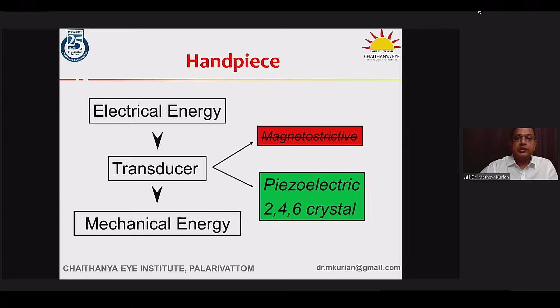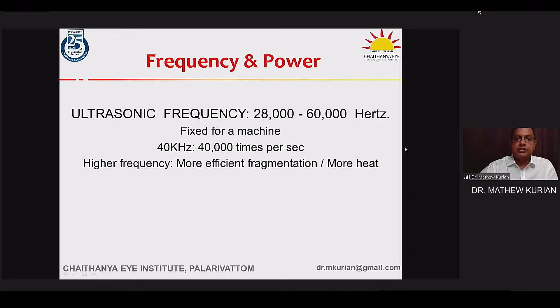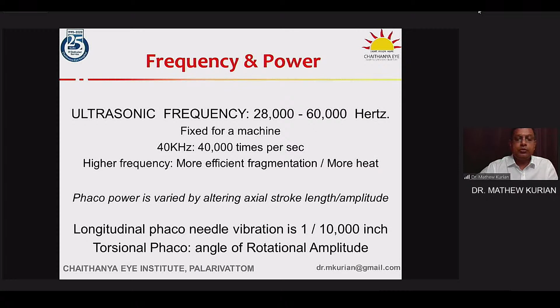But beyond a certain limit, the number of crystals increases the weight of the handpiece and makes it poor in terms of ergonomics. The frequency is fixed for a machine and ranges from 28,000 hertz to 60,000 hertz. Basically, most Alcon machines work at 40, the longitudinal ones work at 40,000 hertz. That is 40,000 times per second the phaco tip is striking the nucleus. Higher frequency certainly is more efficient in terms of fragmentation, but also generates more heat, and so there is always a trade-off in this equation. The phaco power is varied by altering the axial stroke length, or when it comes to torsional phaco, the amplitude of the rotational angle.